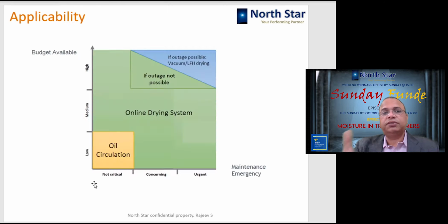Okay, so which method of drying out we should adopt depends, of course, on the budget availability and the situation in which we are. If it is a very urgent situation, moisture content is very high, the stakes are very high, and we have sufficient budget, then we can go for vacuum drying or LFH drying. And if emergency is still there, but outage is not possible, then we can go for online drying system, because it is not required to put your system off during the drying period.